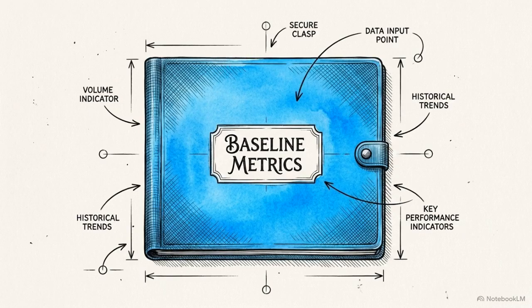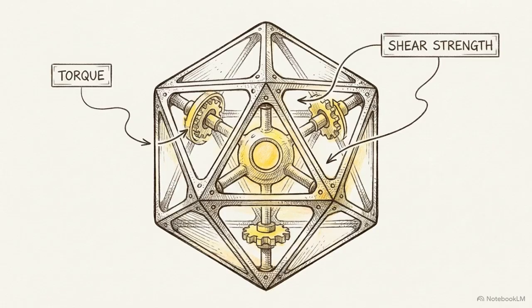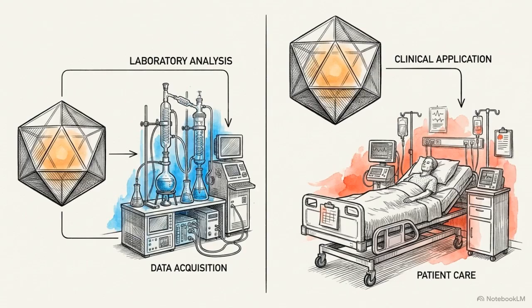Step 1 begins with the state-of-the-art analysis. This document serves as the absolute baseline, dictating exactly which safety and performance parameters must be measured to prove the device works. The limitation is straightforward. If the accepted industry standard proves that similar devices rely on human clinical outcomes to verify their safety, the 510(k) exemption is legally invalid for your device.